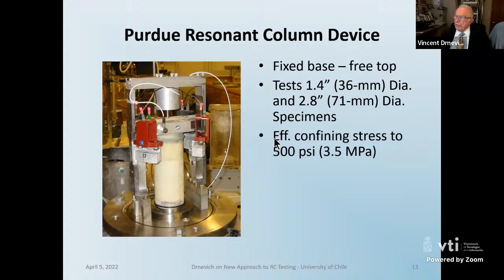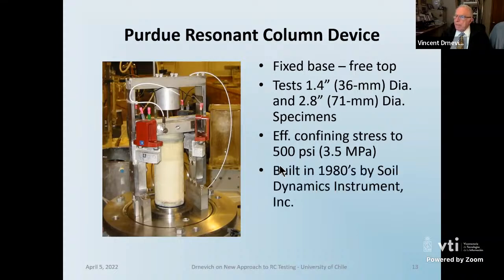The effective confining stress for this apparatus can go up to 3.5 megapascal, which corresponds to several hundred meters of depth of soil if you want to go that high. Normally we work in the 100 to 300 kilopascal range for confining pressures. And it was built in the 1980s by Soil Dynamics Instruments Incorporated. By coincidence, I was the president of that company, and this is the device that I developed. And by the way, the one at Purdue is from the 1980s, so that makes it, what, 42 years old, and it's still functioning very well.